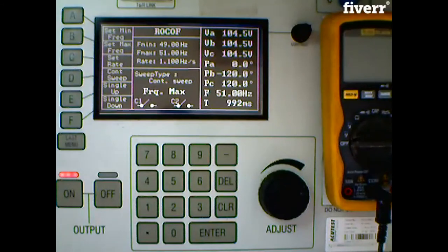That's smashing. Now, for those eagle-eyed people, that just shows you the problem that they've given us: our maximum that we can use for our pickup is 1.025, and we're getting those slower times. Of course, if we were allowed to go slightly higher at 1.1, our times are coming down much quicker. So it just shows that the actual limit they're giving us, 1.025, is a little bit close to the edge, as we've just proven, because we can't get a trip point. But if we were allowed to go up to, say, 1.050, it would trip perfectly. But we're instructed to carry out the tests with the information we're given on the test sheet, and that's what we've done.